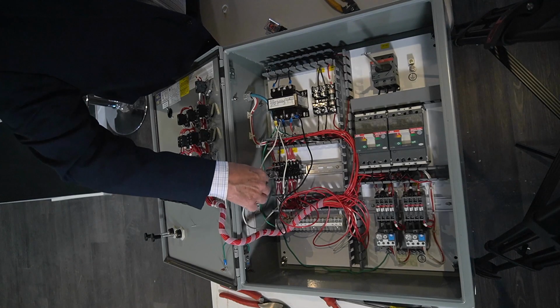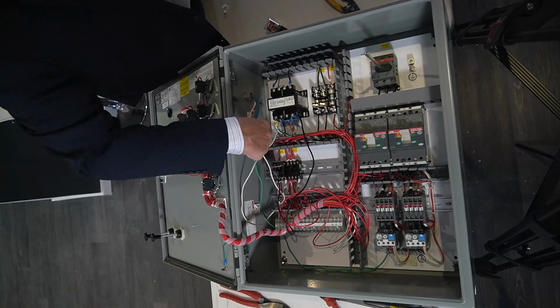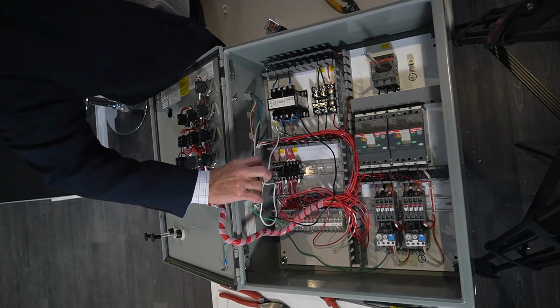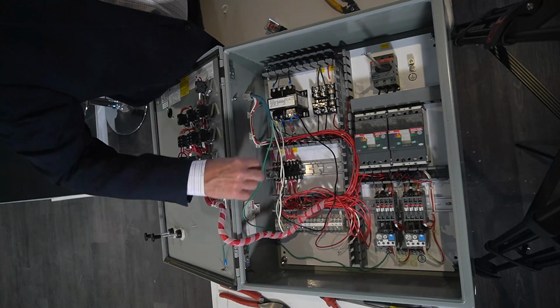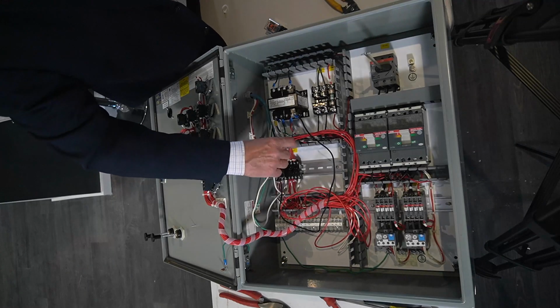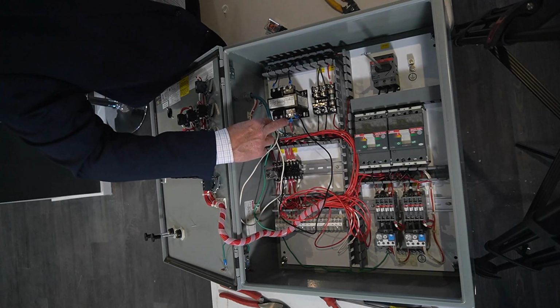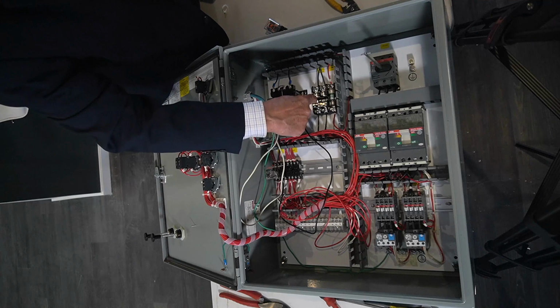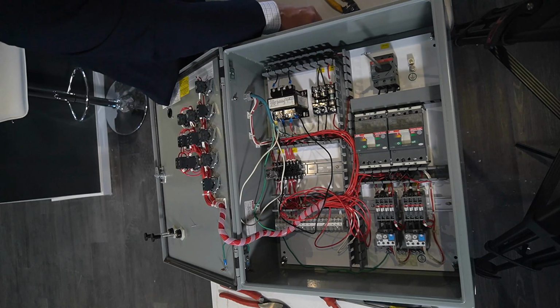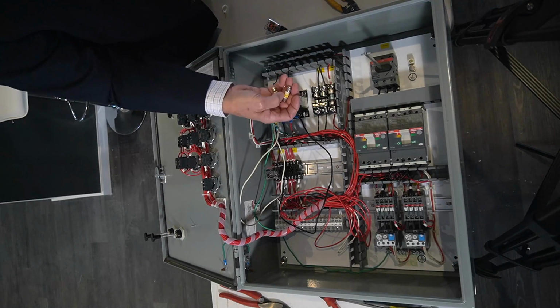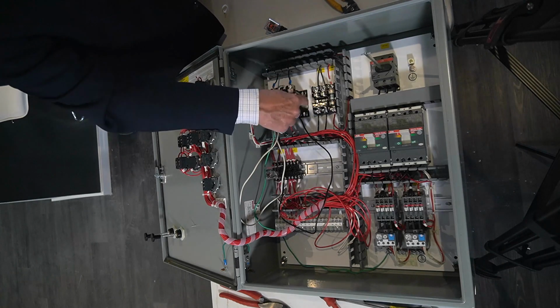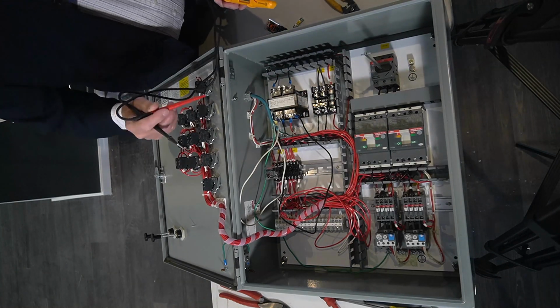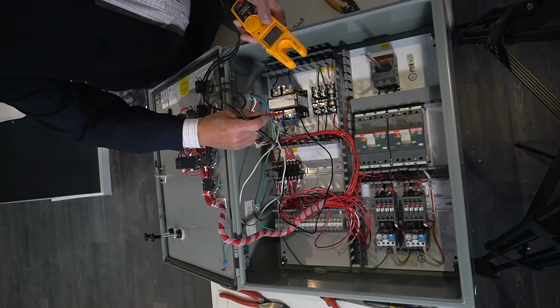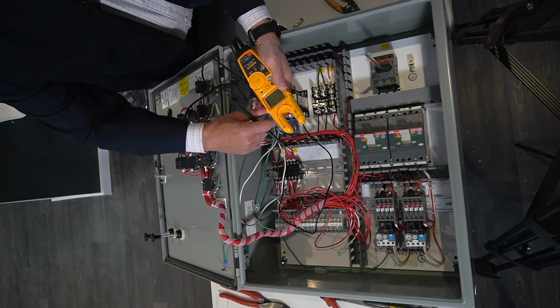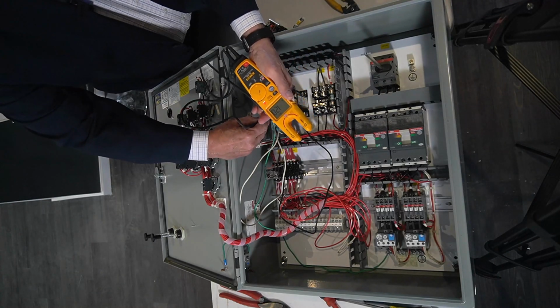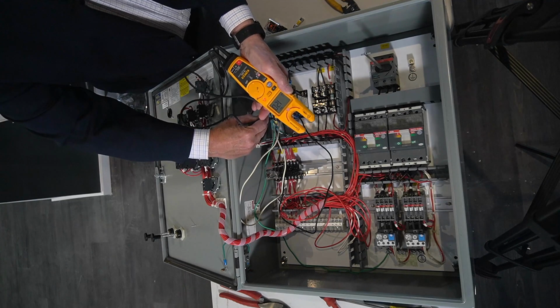I've taken a field wire, brought it in right off of an extension cord. Of course, I've grounded the frame, and I'm taking 120 volts to the secondary of the transformer. I've pulled the high voltage fuses. That would be these fuses right here that would have been in the primary. We're going to apply voltage, and you'll be able to see on the meter that in the secondary I've got 120 volts AC.